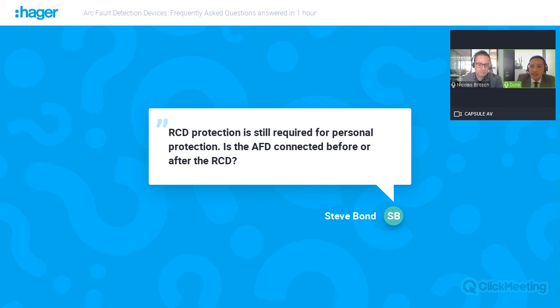In case you want to use MCB plus AFDD in your system, of course, you can have the RCD upstream to protect against differential current, and we complete the short circuit protection with the MCB and the arc protection with the AFDD. So I hope that is clear for you.